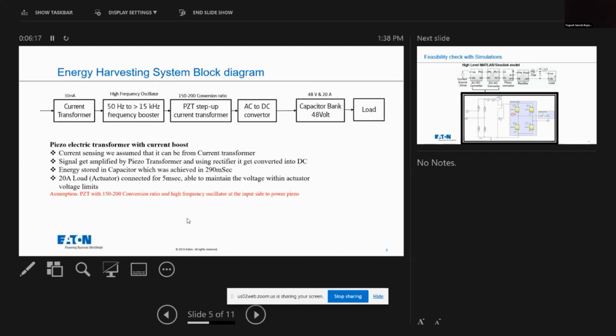There are some additional assumptions, like current sensing. Right now we assume we have a current transformer, then the signal gets amplified by the piezo transformer, and using a rectifier it gets converted into DC. We have less than 300 milliseconds available, and within that time we have to discharge the entire current to the contactor coil.